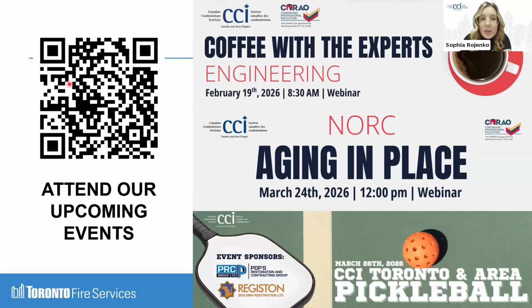Okay, the next question is whether there's any mandatory requirement for residential units to have fire extinguishers. No requirement. Section 6.2 only applies to common areas, not to individual dwelling units. It's a good idea, but don't forget fire extinguishers have their own maintenance requirements. You get it serviced minimum every 6 years.